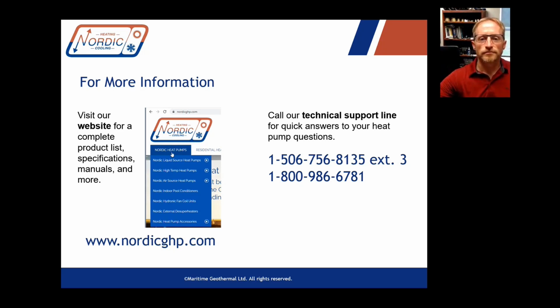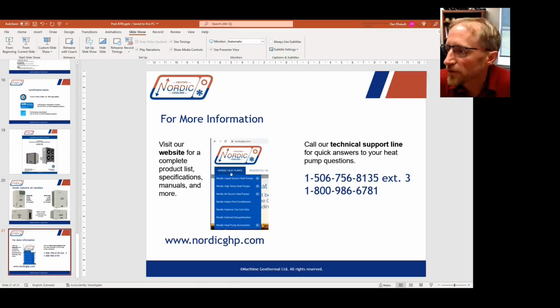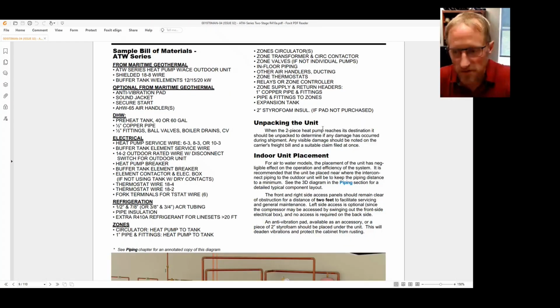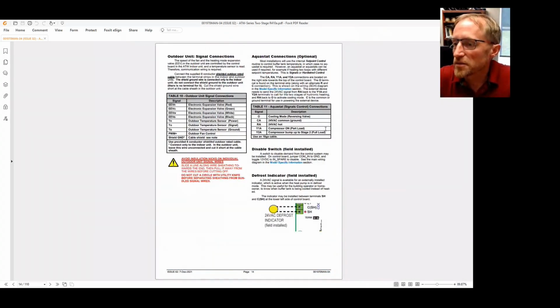Okay. Yeah, it's about chilled water temperatures. So what's the lowest the heat pump can go down to, and then I guess technically what you could store it at? How low could you get the tank to? I think a common temperature to use is 45 Fahrenheit. Sorry for the Fahrenheit again. I don't know what that is in Celsius, but I think it's 7 degrees actually. But you can go a little bit lower. If I open up the air-to-water manual here, which is the one I was just mentioning. And that's actually, the output of the heat pump or the max storage?